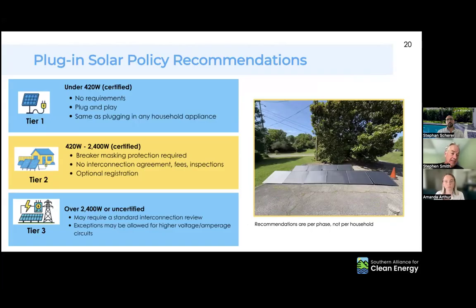From a SACE perspective, here are the policy recommendations underway: under 420 watts, there really is no serious safety issue at all, as long as it has the certified inverter, and it should just be plug and play, like a household appliance. As you climb above 420 watts, you've got to be somewhat more aware of breaker masking issues. But we don't believe that up to 2.4 kW, or 2,400 watts, you really need all the provisions of a typical interconnect agreement that a lot of utilities are requiring.